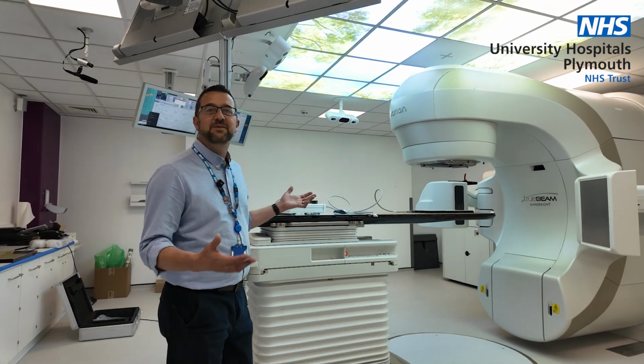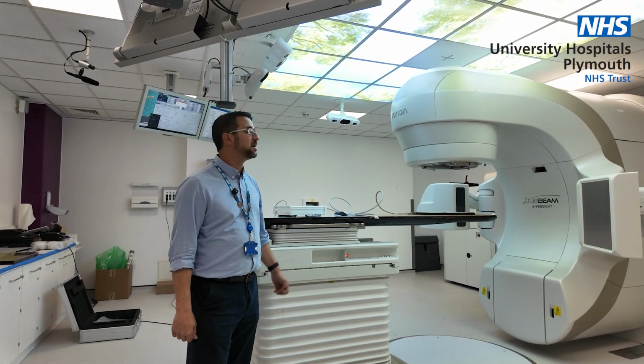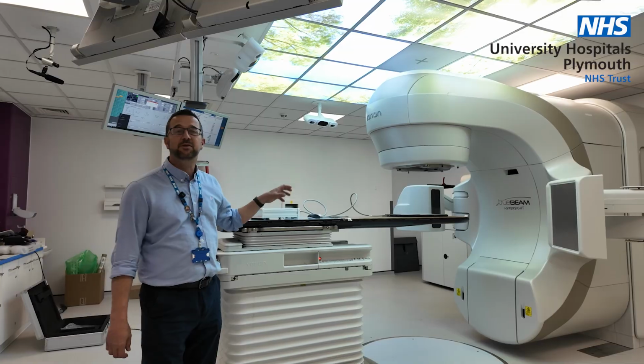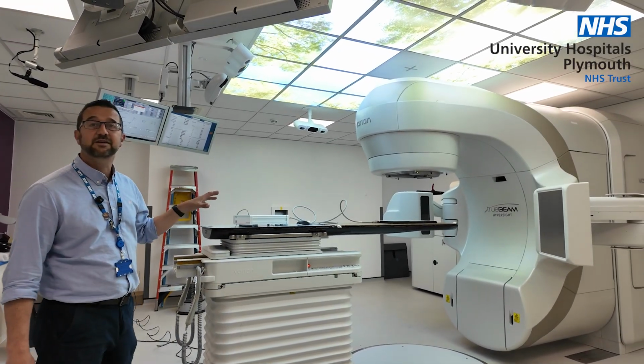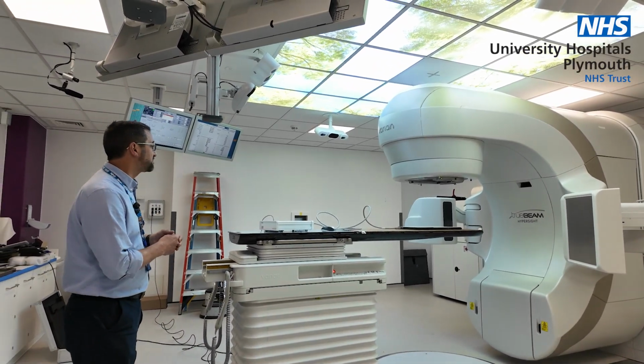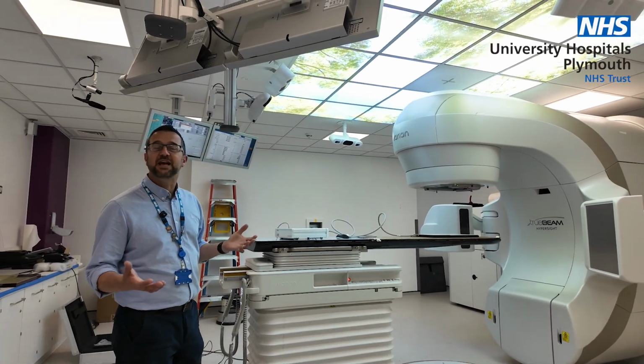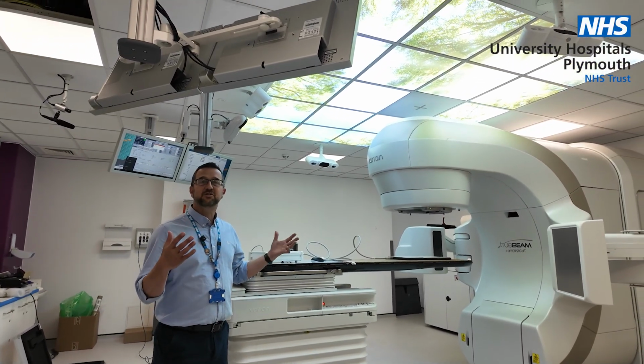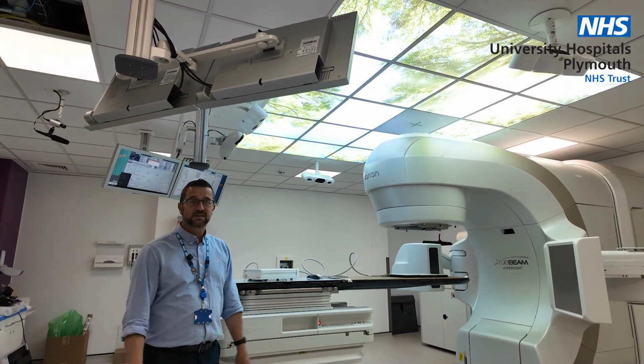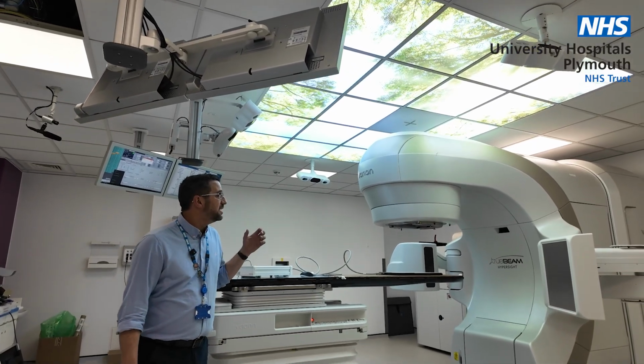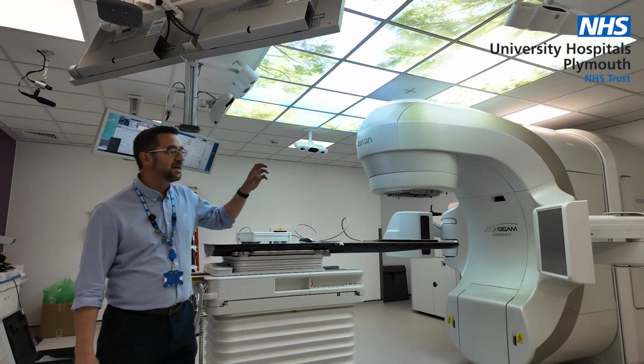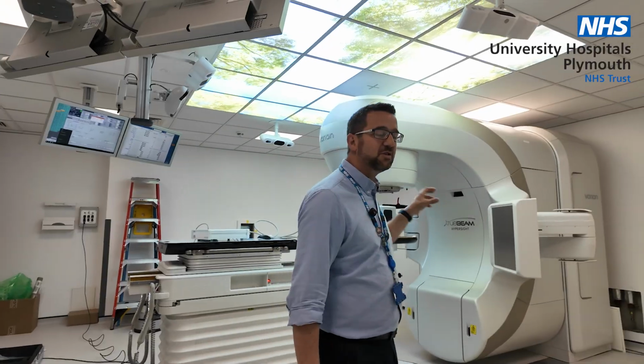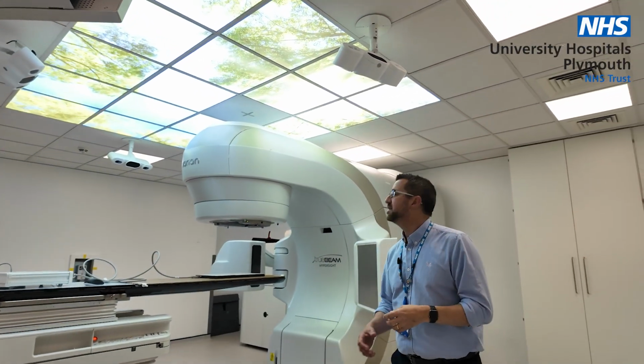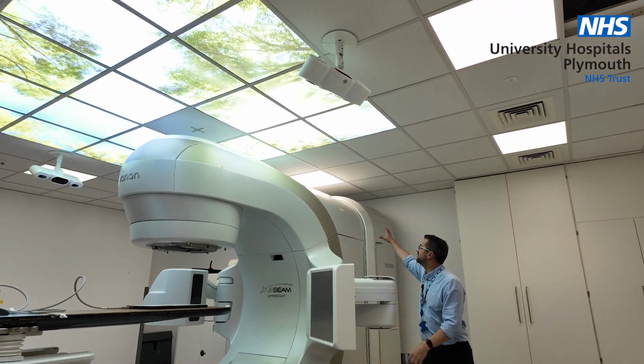So this is an external beam radiation linear accelerator made by a company called Varian. This is the TrueBeam model. This is our newest linear accelerator we've got. Everything starts off as electrons. So without electrons, without the electron gun, nothing works. So we start off by generating electrons via thermionic emission. This comes from the electron gun, which is in this part of the machine here.